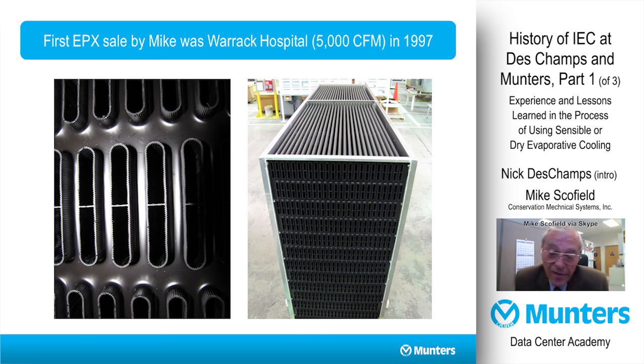Anytime you have a surgery or a hospital application, typically in California, and I think it's the case throughout the United States, we need 100% outside air for surgery. This system is an excellent application of dry evaporative cooling and has a tremendous impact now in California, because with a 70% wet bulb depression efficiency, which is the approach of the wet side wet bulb to, or I should say, the approach of the ambient outdoor air dry bulb to the wet side wet bulb.